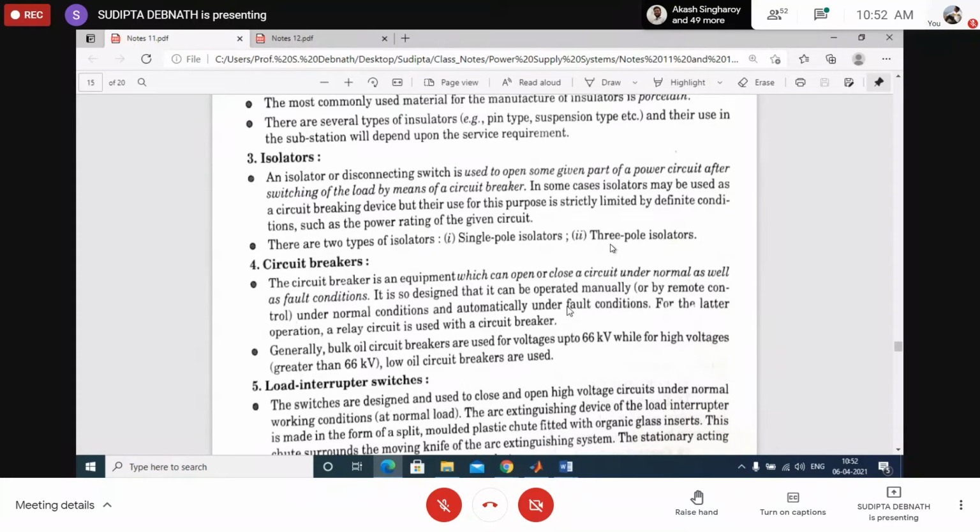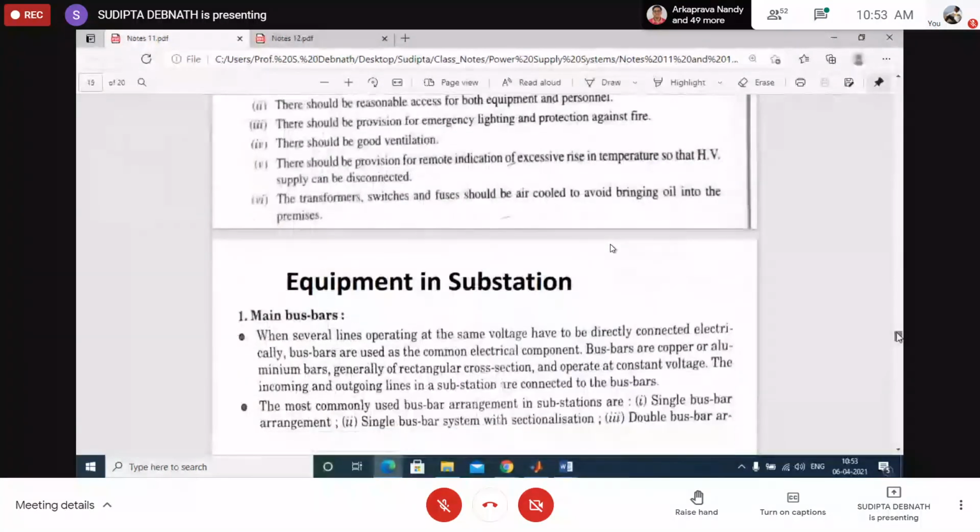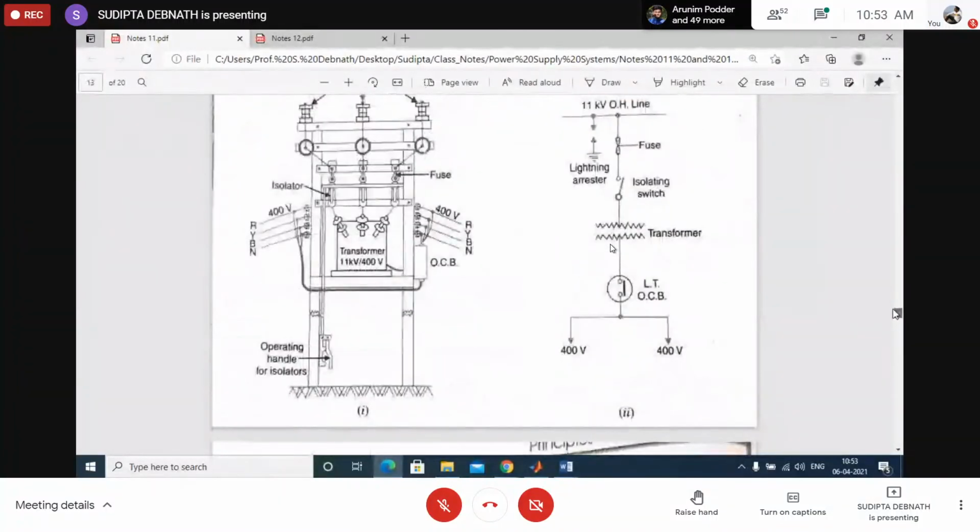I will discuss those. So, and also suppose the circuit is open. You need to put that circuit in operation. You have to connect the circuit by circuit breaker. Okay. So, what is the use of isolator? See, whether the circuit breaker is connected or it has tripped, you will never understand from outside. But by observing the isolator, suppose some maintenance personnel, how will they know that yes, we can now do the operation work? They can understand only by observing the isolating switches.